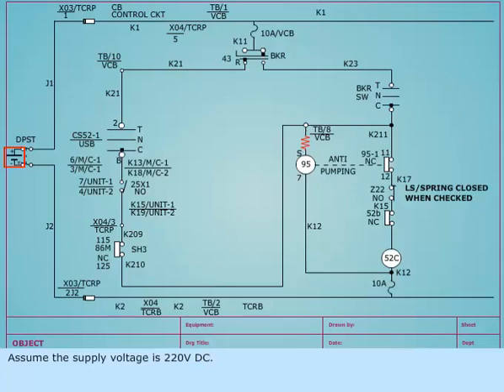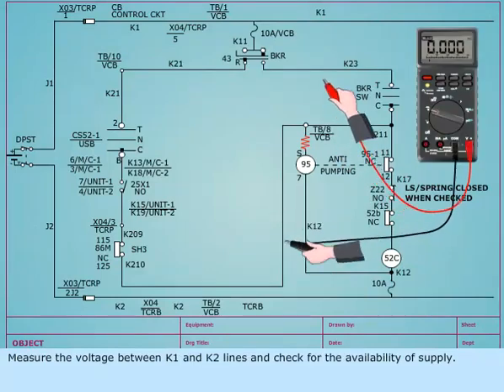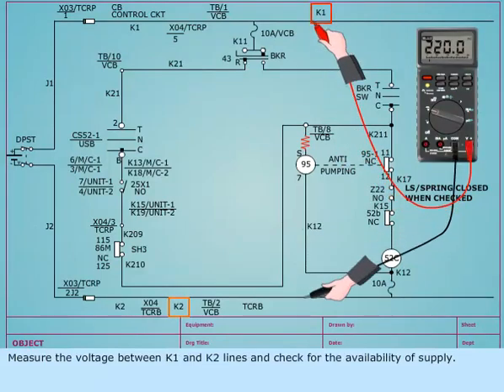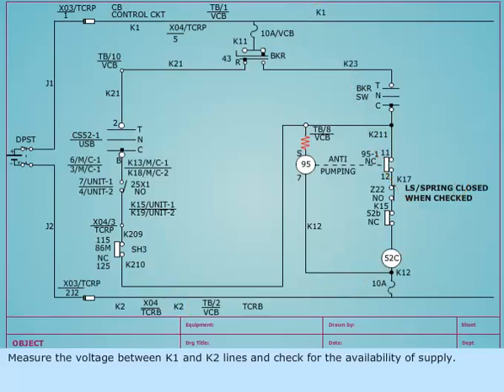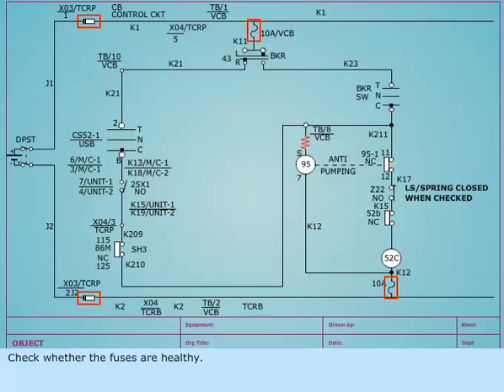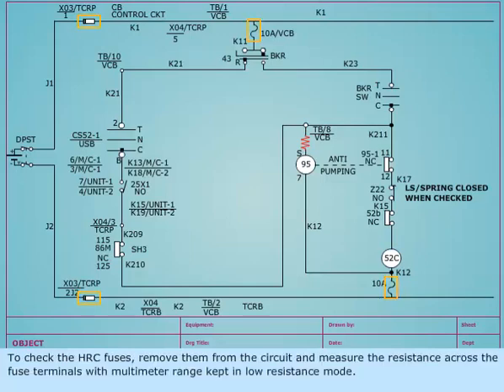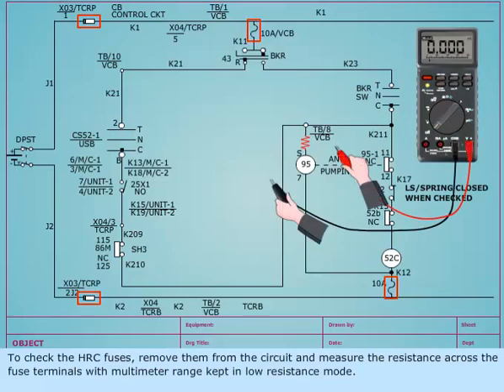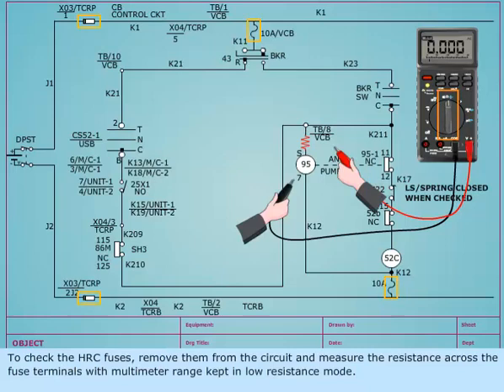Assume the supply voltage is 220 volts DC. Measure the voltage between K1 and K2 lines and check for the availability of supply. Check whether the fuses are healthy. To check the HRC fuses, remove them from the circuit and measure the resistance across the fuse terminals with the multimeter range kept in low resistance mode.